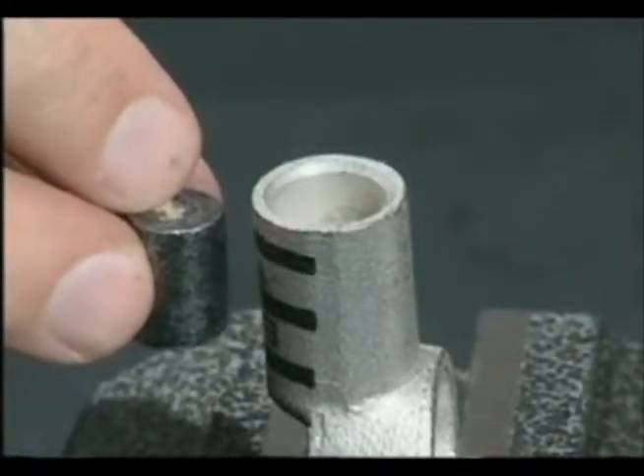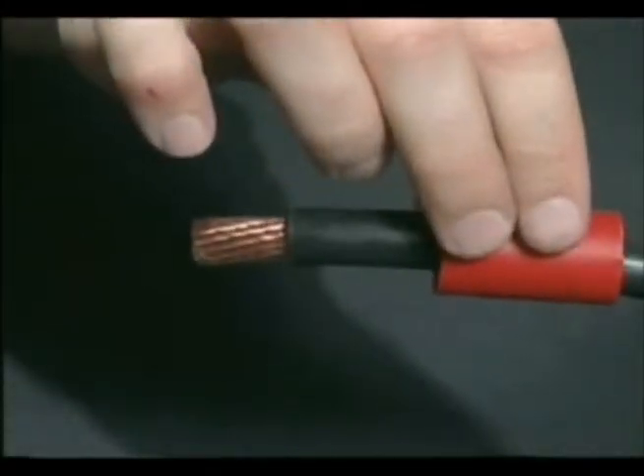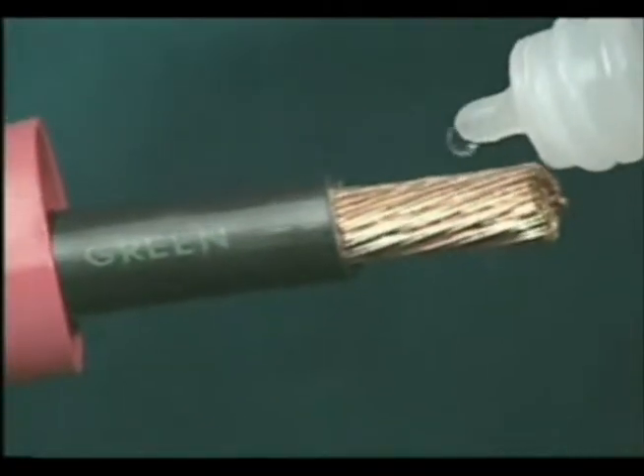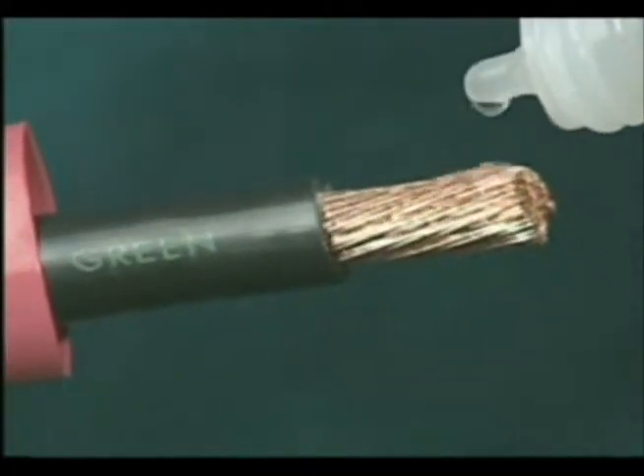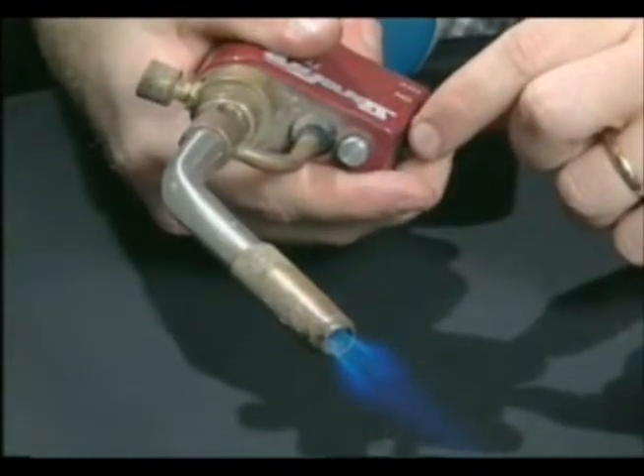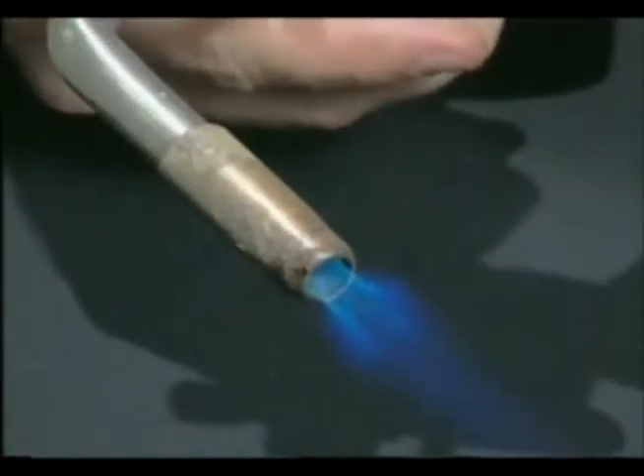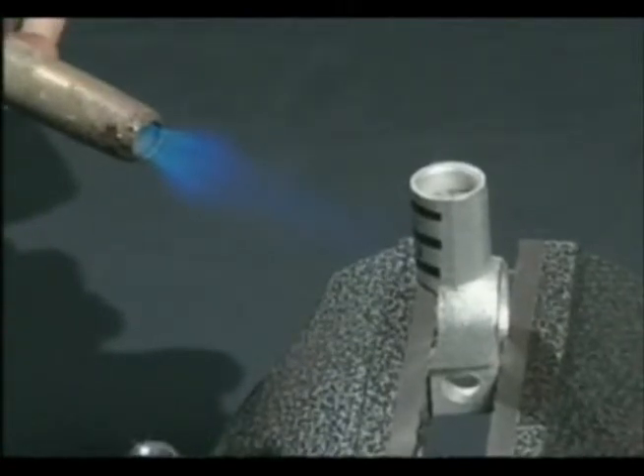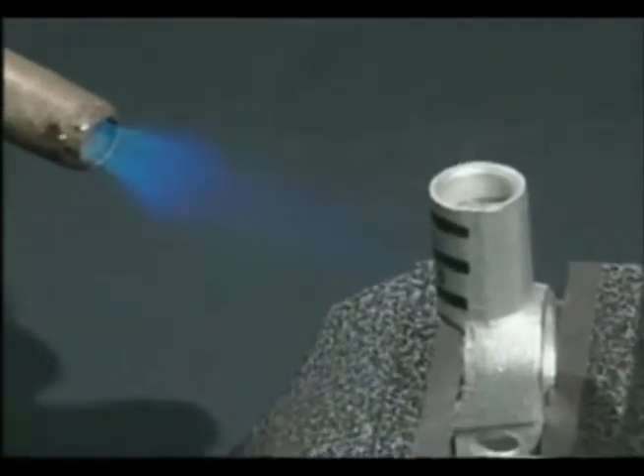Place the solder pellet into the barrel, slide the heat shrink tubing over the cable, and apply several drops of flux to the exposed wires. Preheat the solder pellet in the terminal for the length of time indicated in the written installation instructions.